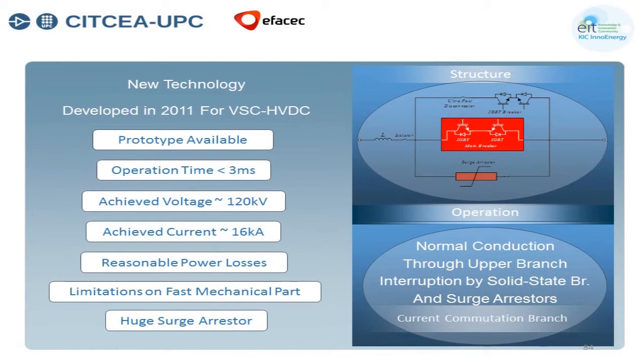But I think one of the most interesting topologies for HVDC circuit breaker, which was introduced in 2011 by ABB, is the hybrid breaking concept. So you have this mechanical disconnector here, which is supposed to be a fast mechanical disconnector, and you have small size IGBTs here. Then you have a full solid state breaker branch, which is ready for interrupting the full fault current, and you have a surge arrestor branch, and you have a fault current limiter inductor here.